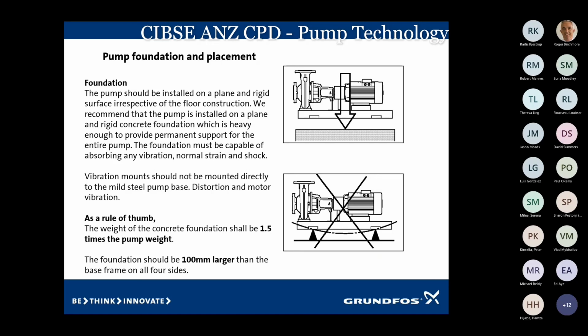If you mount that steel base onto a concrete foundation and it's not wide enough, the bolts where you fasten the steel base to the concrete can break away, and it'll chip that concrete away. It'll set up vibration, and it'll destroy itself. We had a 90 kilowatt motor. It did that. One of the back end securing down bolts wasn't there, and within 3 months the motor bearings were frozen onto the shaft. They had to gas cut the bearings off. So vibration will really take off.